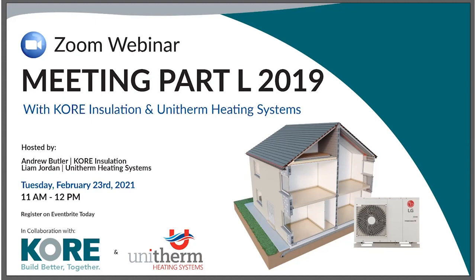But the COPs - there's a lower degradation COP on the Therma V. Even down to -7, we're still getting 3.13 COP, and that's very good. The seasonal COP is 4.45. I think on the split units it's around 4.1, 4.2. So yeah, that's the difference. If you want to send me an email, I'll clarify that with documentation.